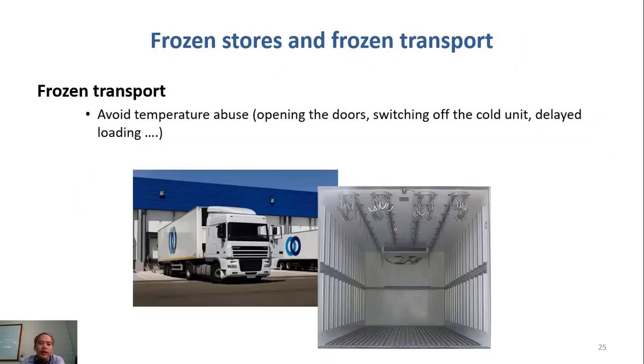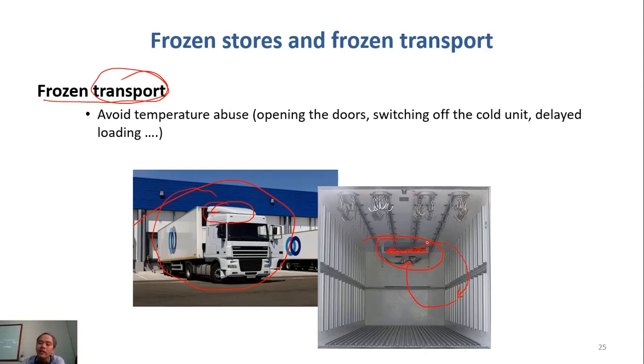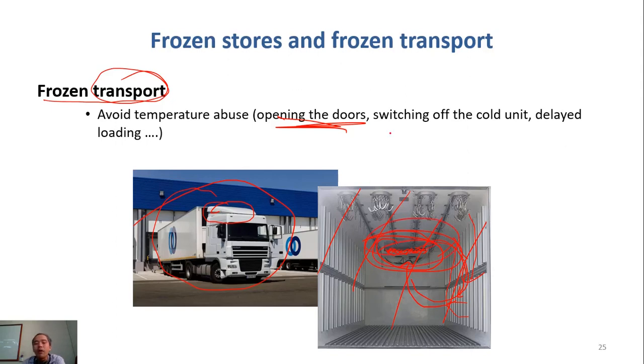For frozen transportation, we use cold trucks equipped with a cooling system. The system blows cold air onto the food, the air returns and loses heat to the evaporator, and is then cooled again. Normally, the cooling power in these trucks is not very strong. If you open the door for a long time while loading product, the temperature inside will rise significantly and it takes quite a long time to recover, because the truck's system is designed only to maintain low temperature, not to freeze food.